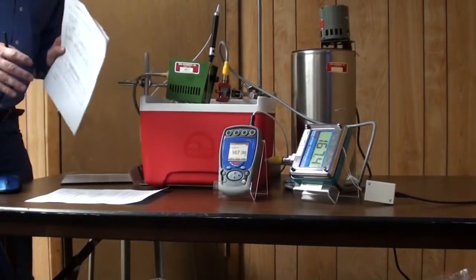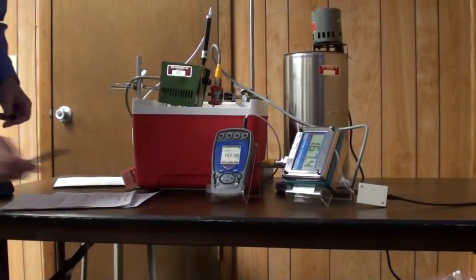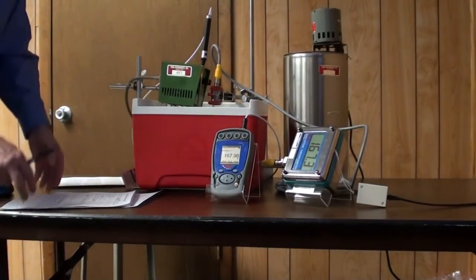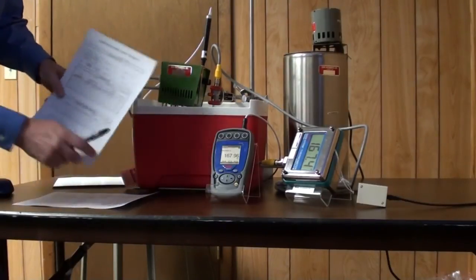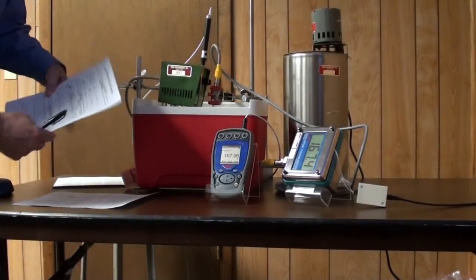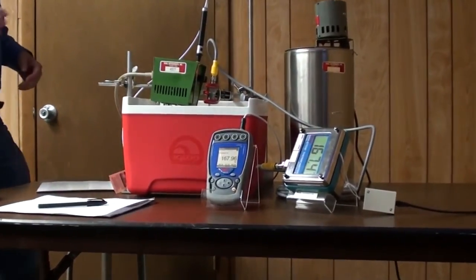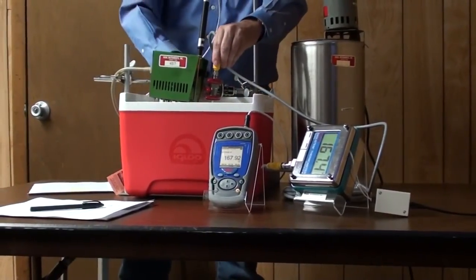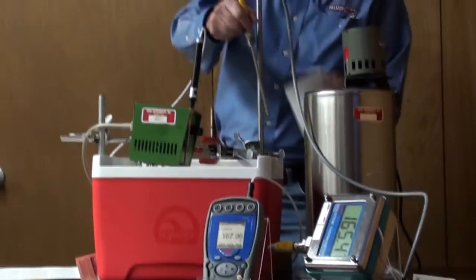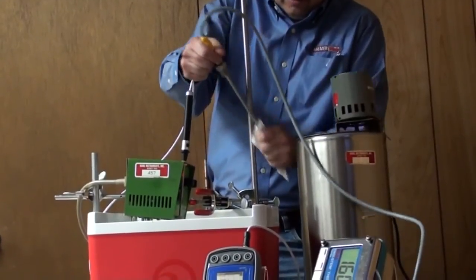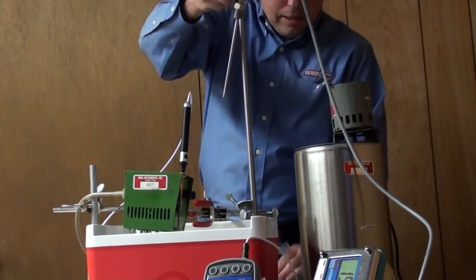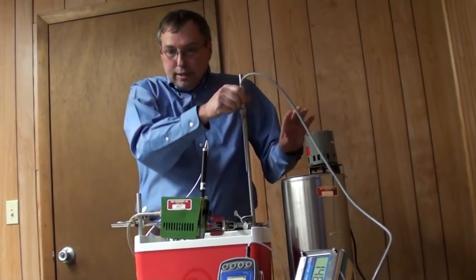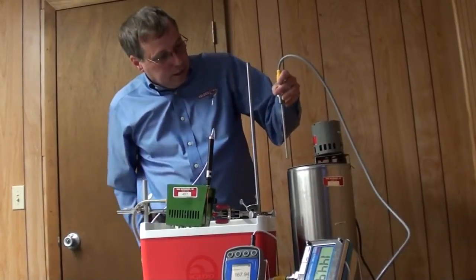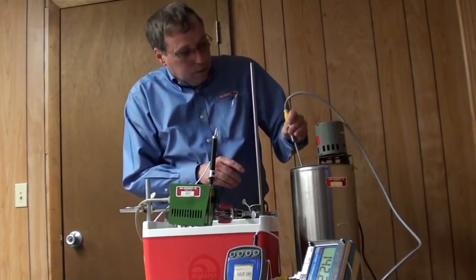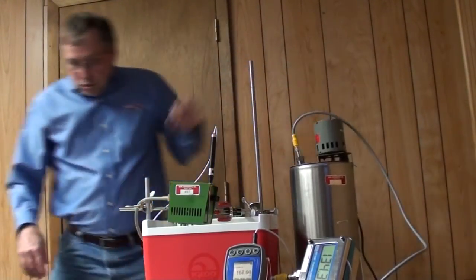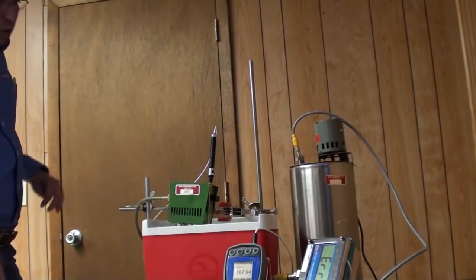Now, this is not the norm for our units. I purposefully miscalibrated that unit prior to our show here so that we could go through the calibration. So we have a reason now. We're off by a half degree, and we want this thing a little tighter. So the procedure for doing that, I'm going to take my standard probe out of my hot bath, and you'll see our temperature dropping down on this thing. And basically I'm going to turn the ice bath on, and again it's kind of loud. I don't know if you'll hear me or not. I think so. But I will turn the ice bath on and let this guy stabilize, and that will take us a minute or two.